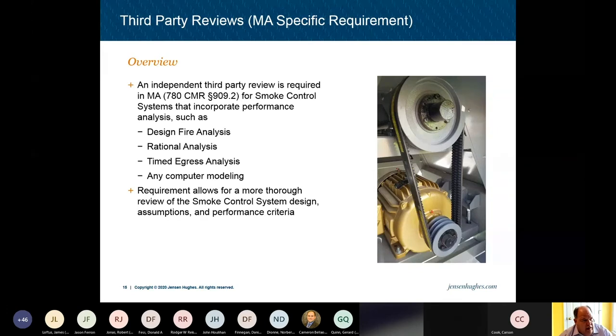Massachusetts also has a requirement that's unique to themselves in any of these new buildings with performance-based smoke control systems like atriums. You actually need a third-party reviewer, and that third-party reviewer looks at the design fire analysis, looks at the rational analysis, the timed egress analysis, any computer modeling that needs to happen. These systems are a lot more sophisticated, and it's very difficult for local jurisdictions to kind of give it proper reviews. Even Boston, who have 3 fire protection engineers on staff, kind of uses the third-party review because it's a code requirement in Massachusetts. But it does allow for a little more thorough review of those smoke control designs, assumptions, and performance criterias.